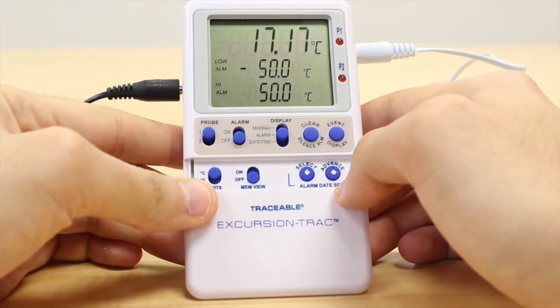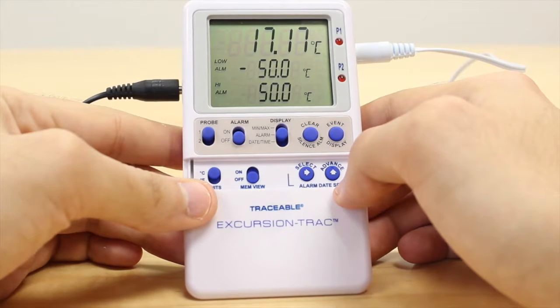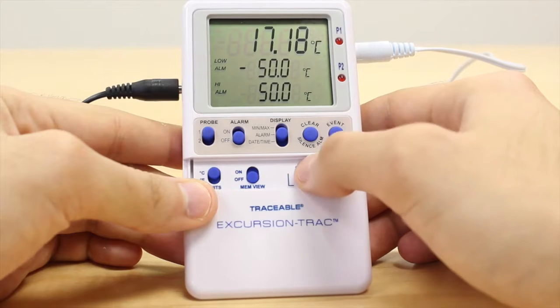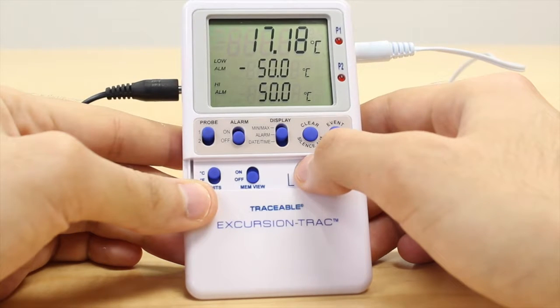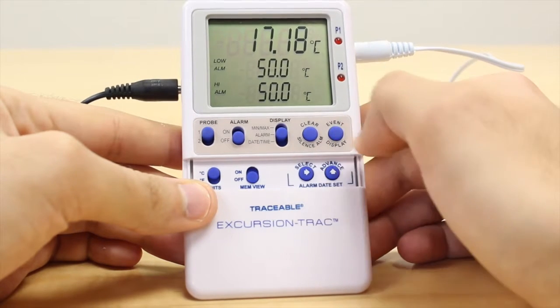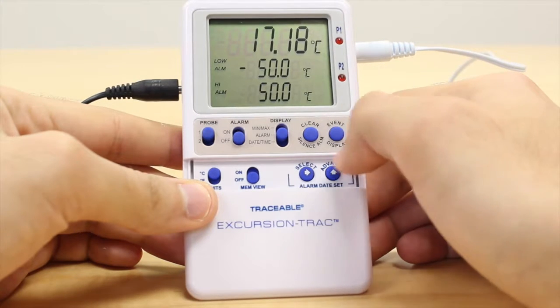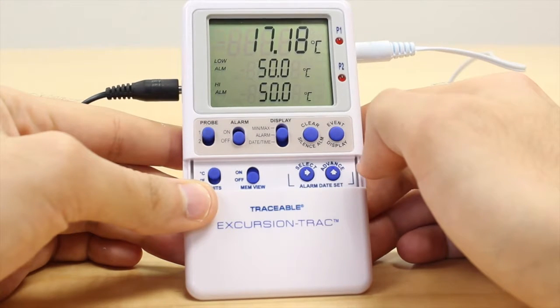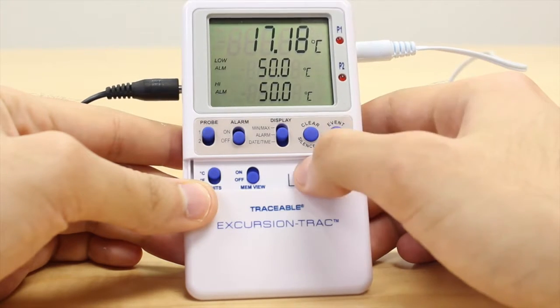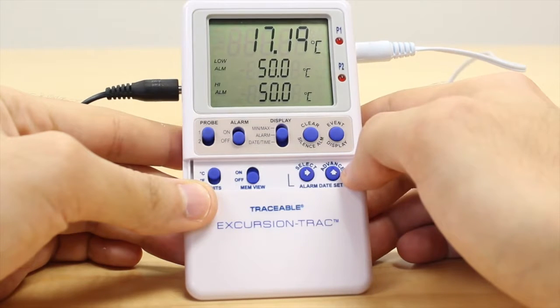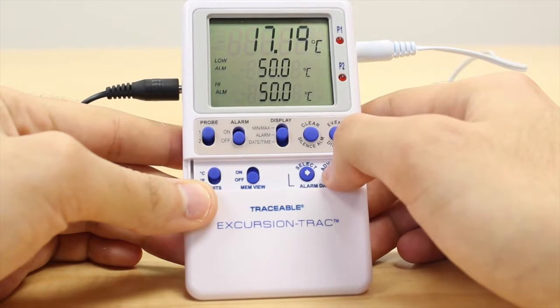So now that we know how Select works, let's use the Advance key with it. For this example, I'm going to set my low alarm to 2 degrees Celsius and my high alarm to 8 degrees Celsius. Like before, the first press of the Select button takes me to the negative symbol of the low alarm row. Use the Advance key to toggle between the options. In this case, it's negative or positive. Remove the negative to keep it positive and then press Select to move on. This digit needs to be removed as my temperature here will be 2 degrees. Use the Advance key until it goes away.